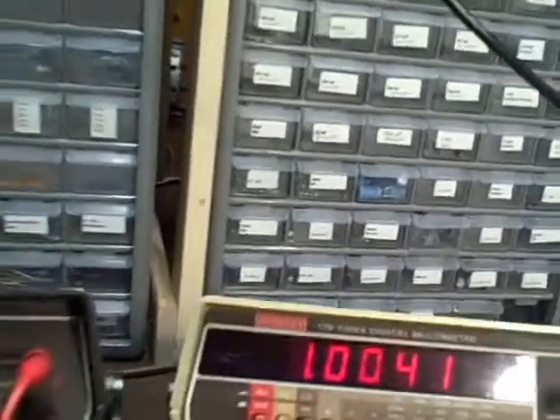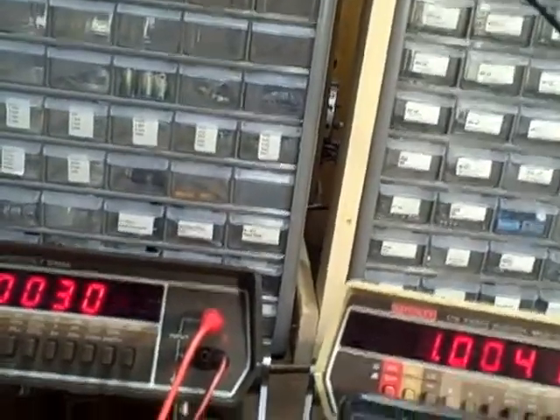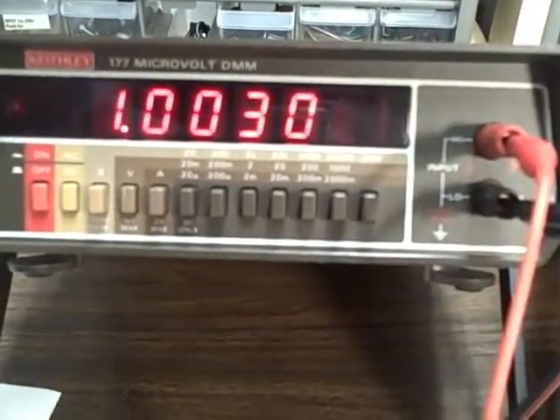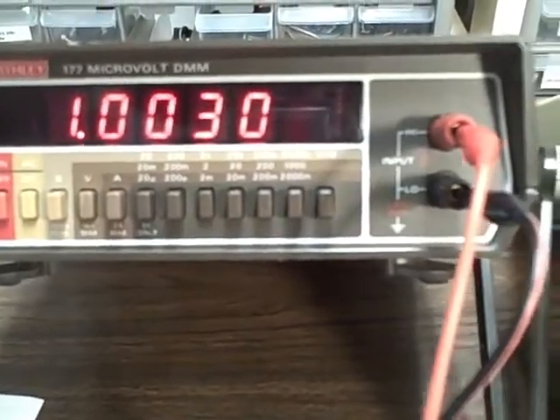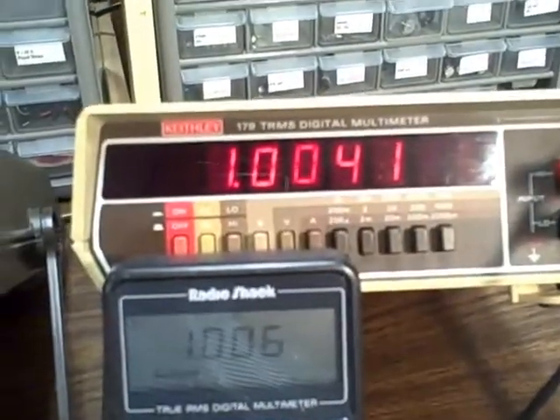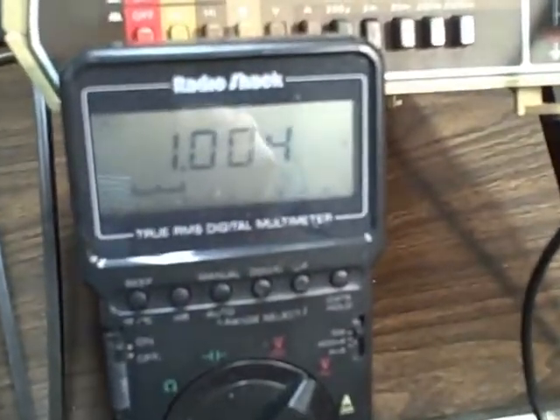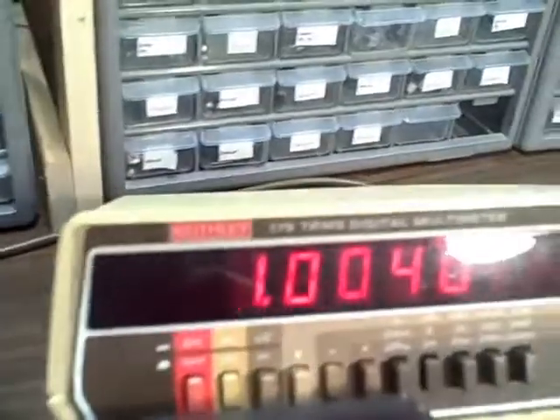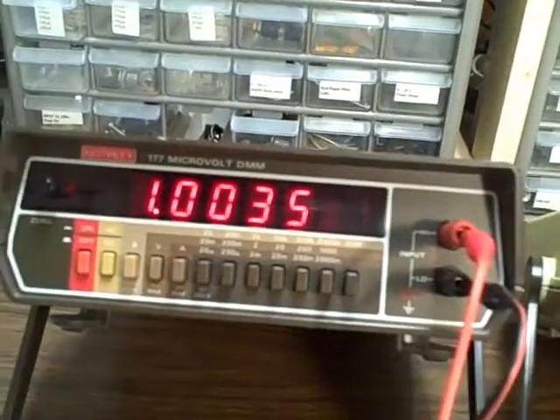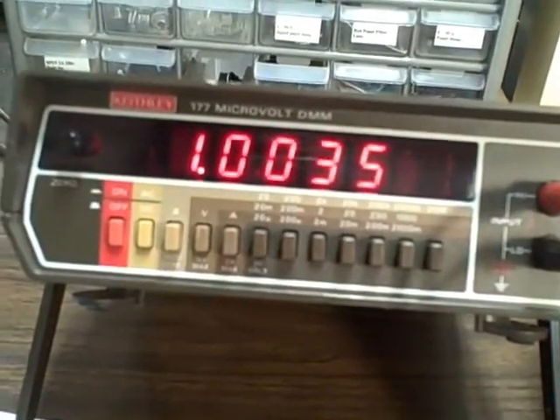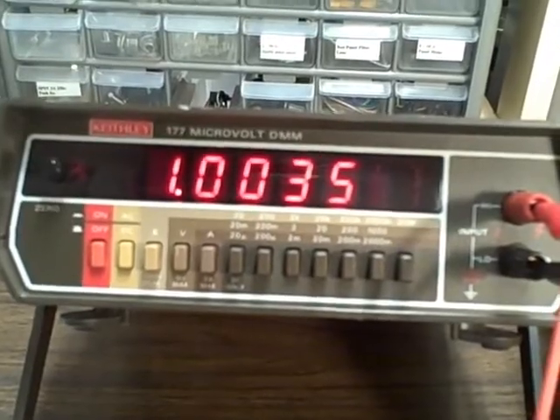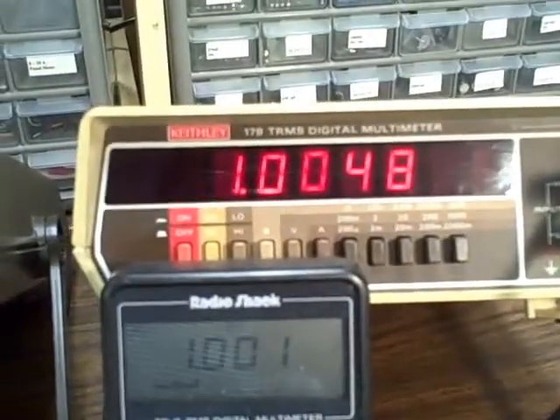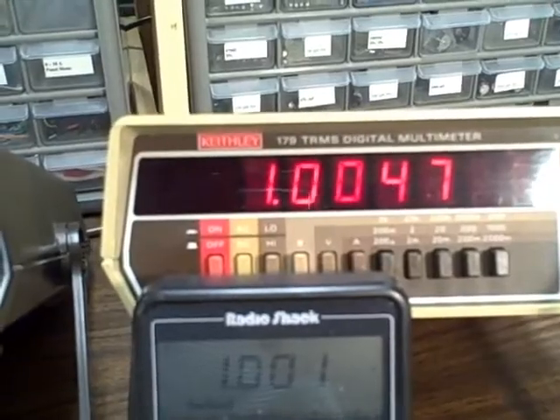We're going to go ahead and turn her down in frequency. We're now reading 1,000 hertz, and the 177 is reading 1.003, the 179 is 1.004, so we're within a millivolt. The Radio Shack is 1.004. And then we'll go down one more range. We're back into the 100 hertz range, and we have the 177 reading 1.0035 or 6, and the 179 is reading 1.0046 or 7.